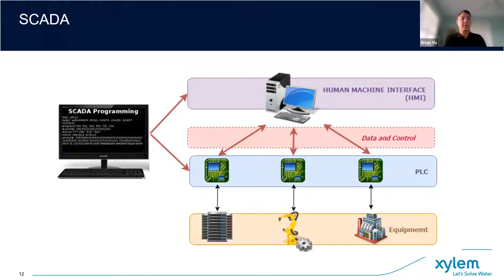Some of the four main components of SCADA are inputs from your equipment out in the field, remote telemetry used for controls, some type of human interface so we can see and visualize, and some type of communication so we can get back, communicate, and control things remotely from SCADA. This is a display of how it works: equipment out in the field talks to a PLC with control logic in it, bringing in data and the ability to control that equipment remotely through a human interface, usually laid out in some computer format.